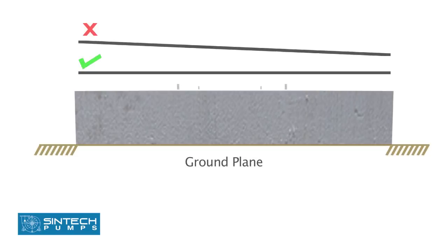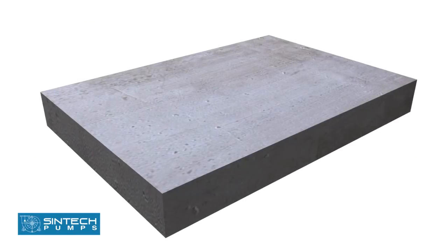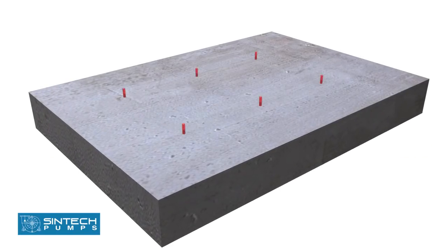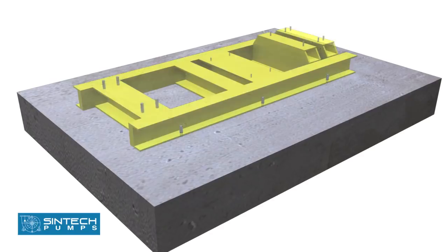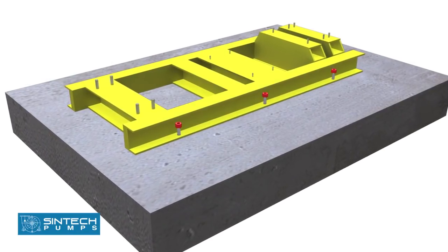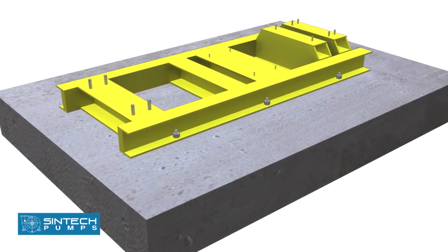The foundation has to be absolutely straight without any inclination or tilting on any side. The foundation bolt of proper size should be embedded in the concrete and base plate tightened, ensuring that it is level in all directions.